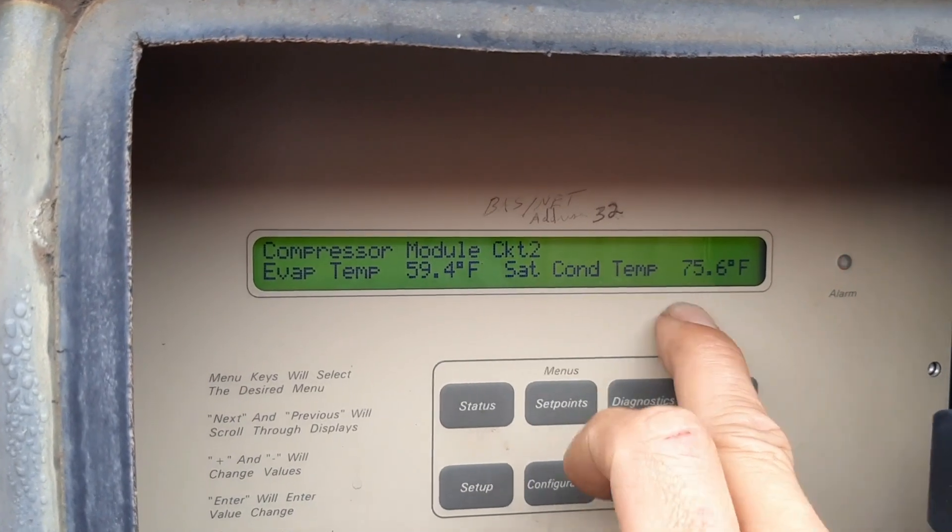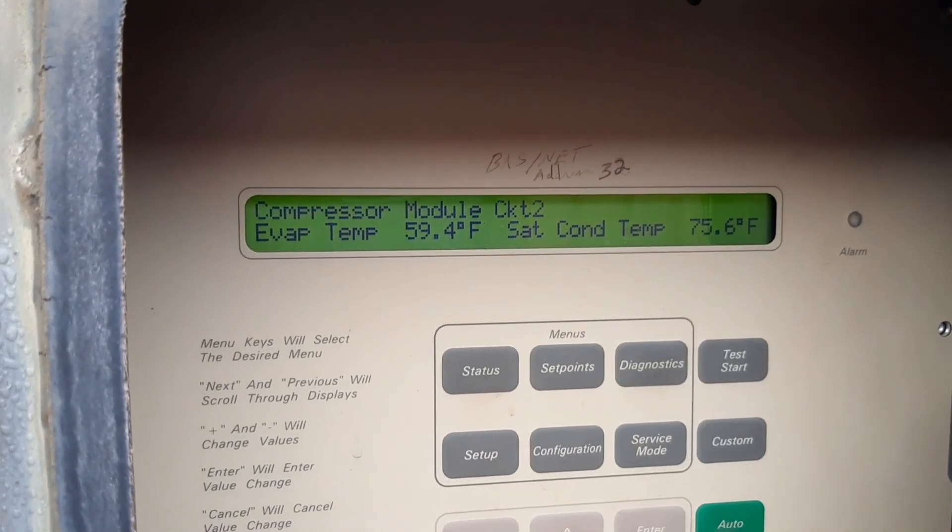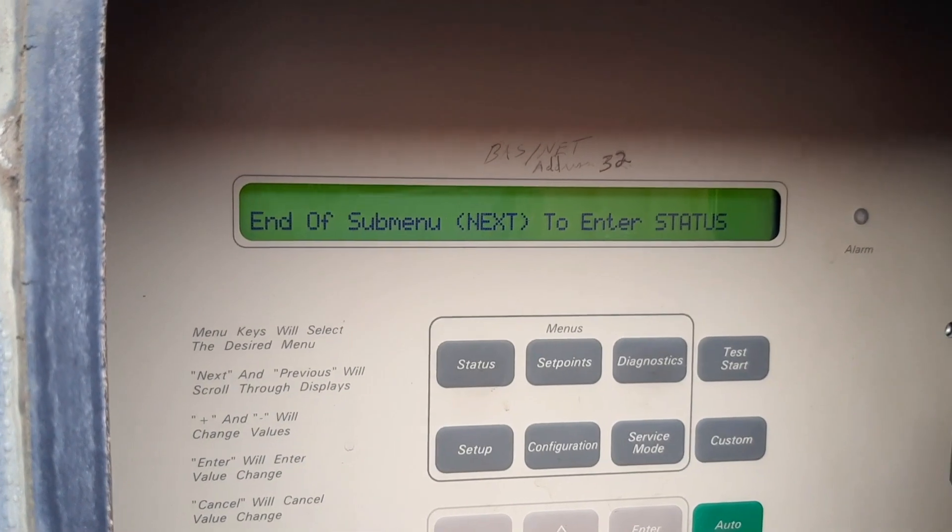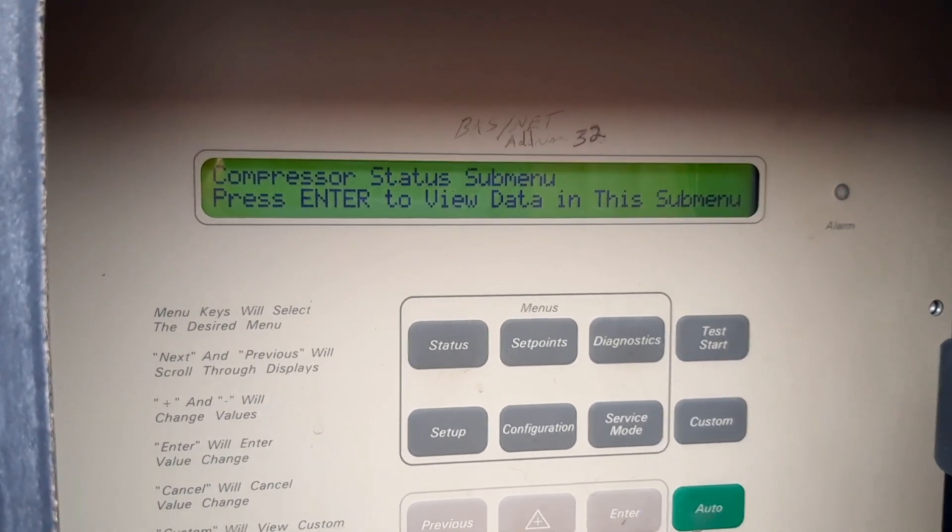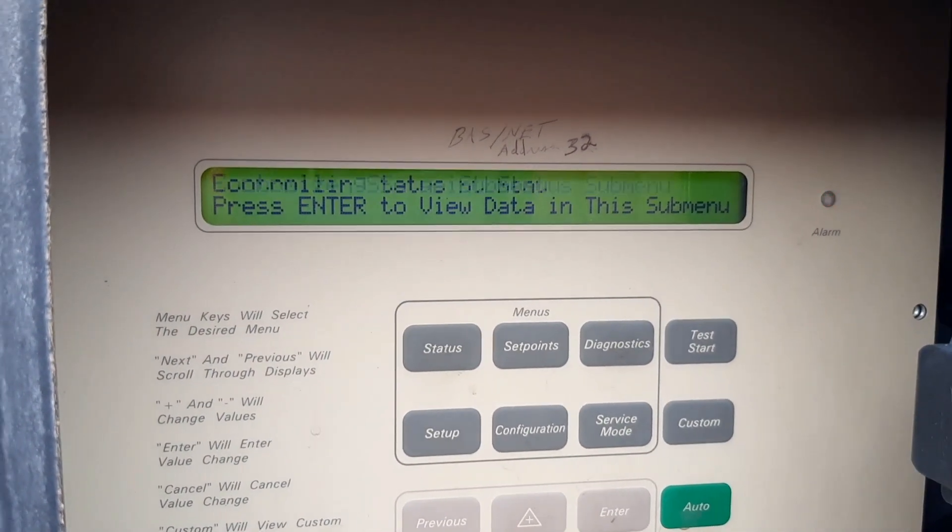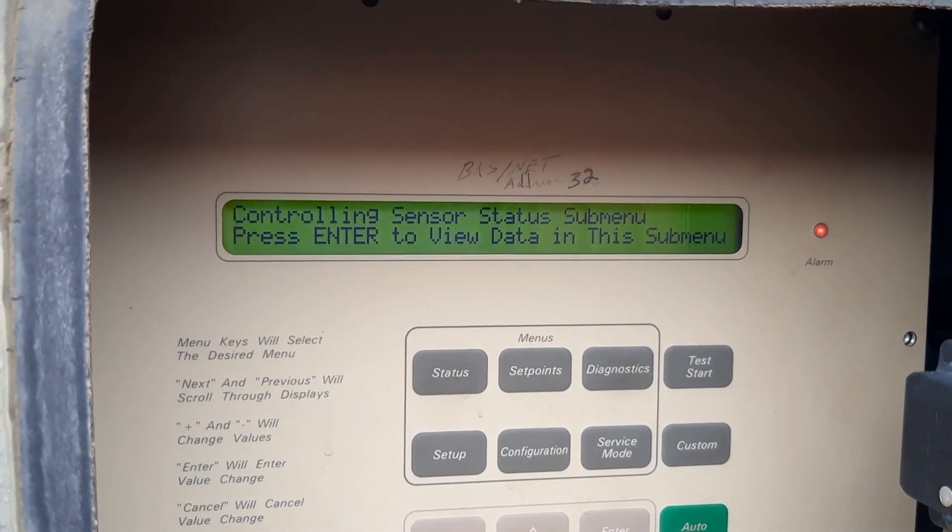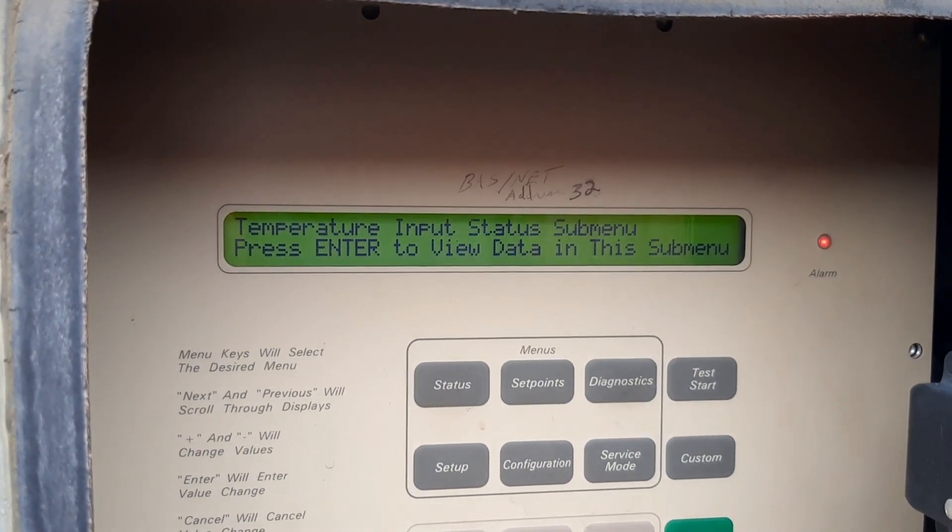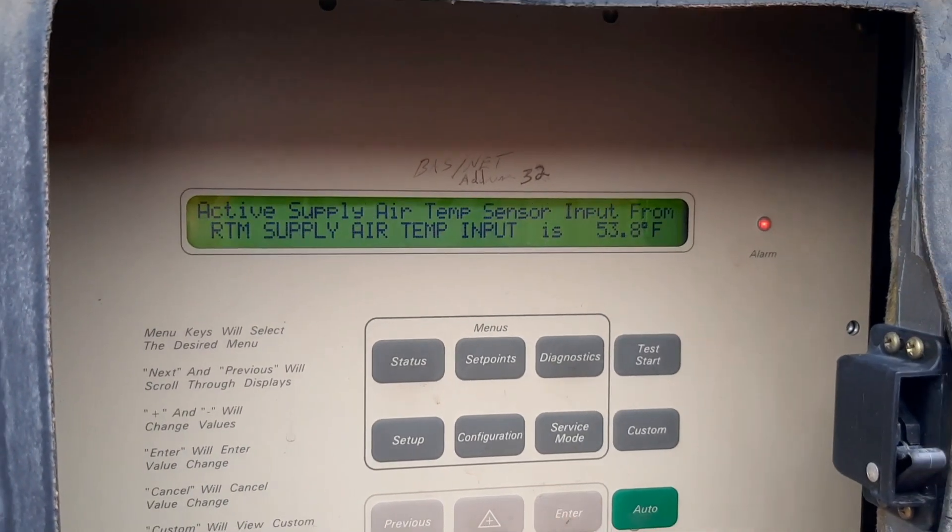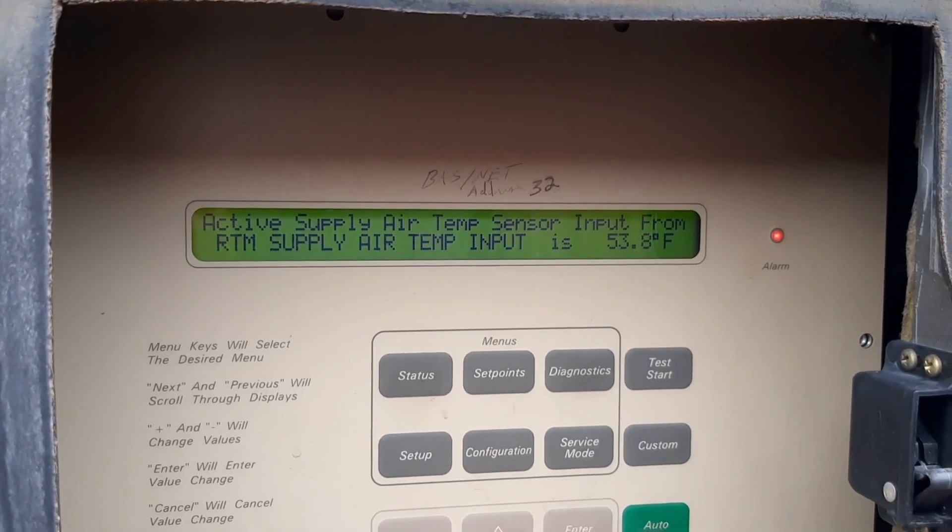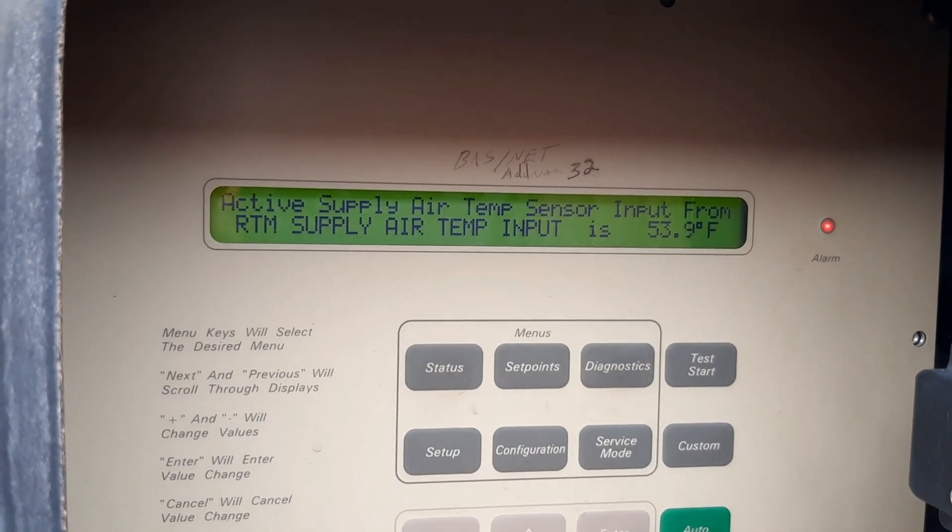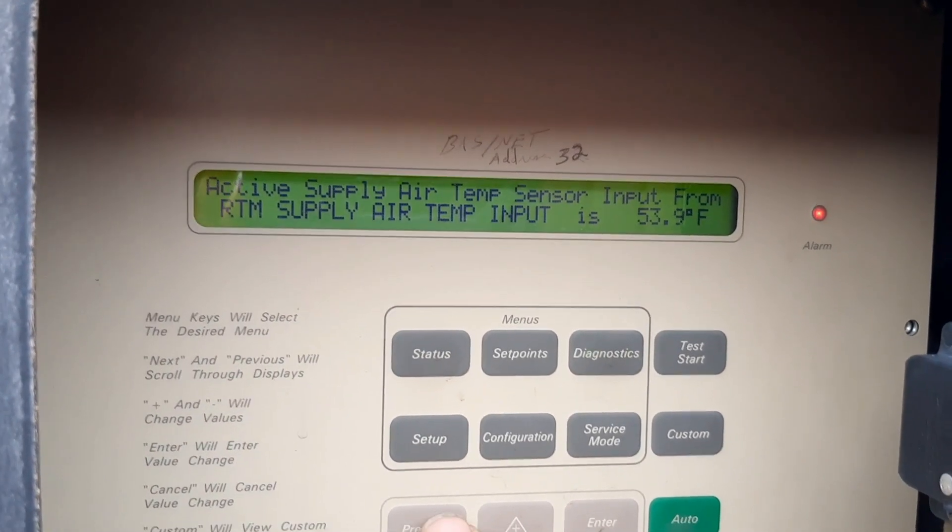Evaporator temp 43, condensing temp doesn't look bad. That's circuit two, so I only got one compressor on that one, that's why that's down. Supply is 53-54, should be pretty sure we're set at 55.